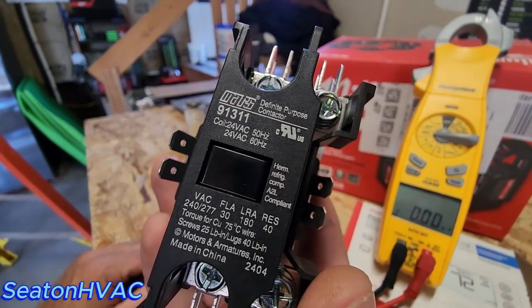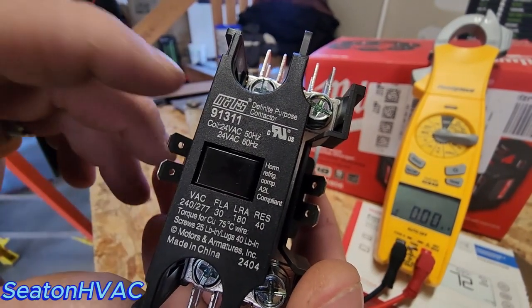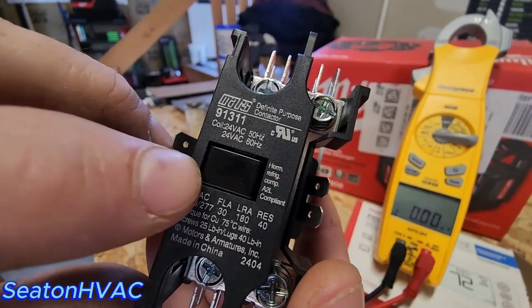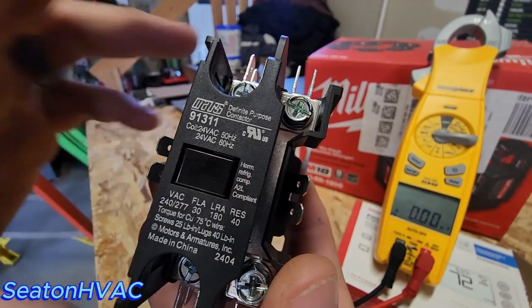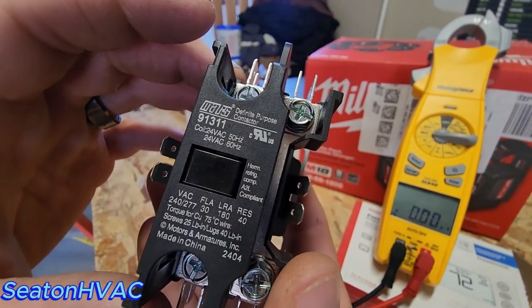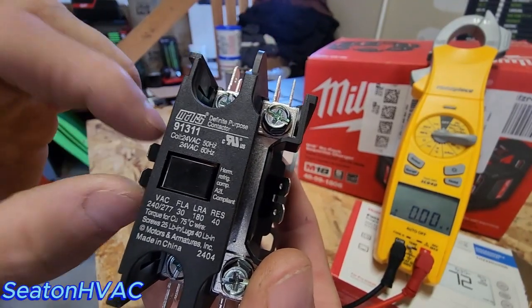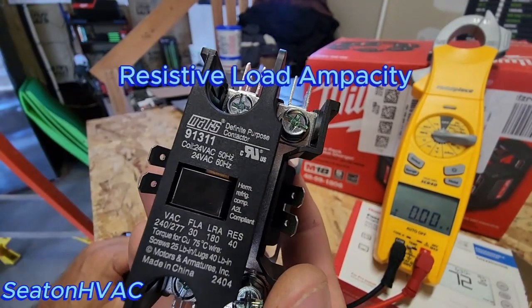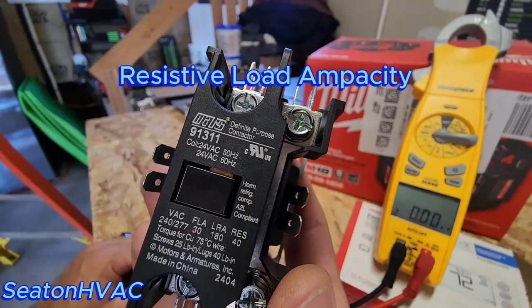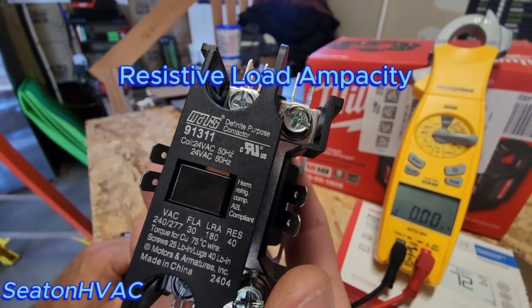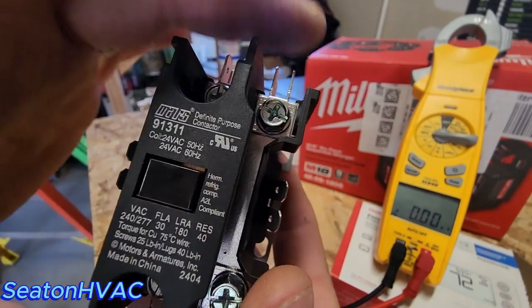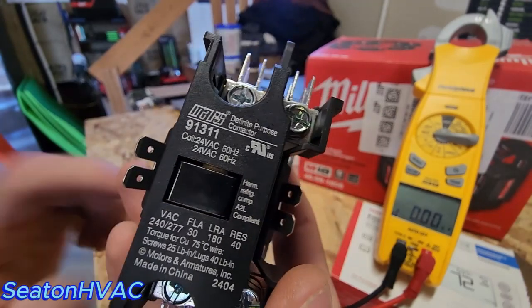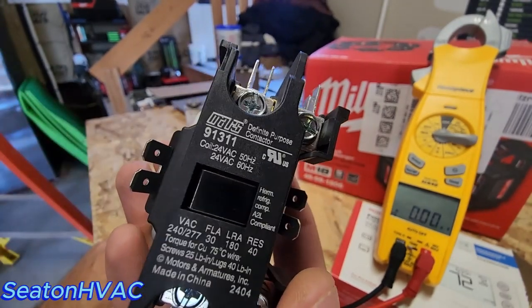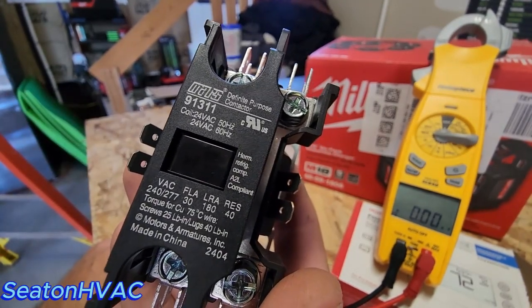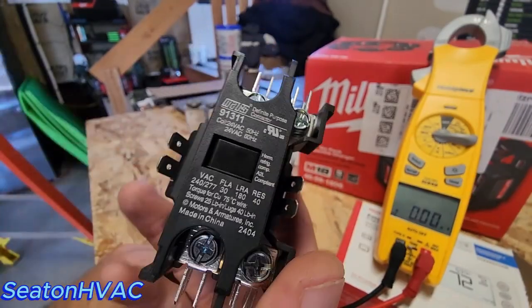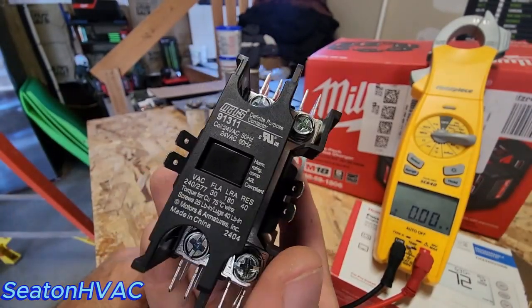It's different than what your full load amps would be. This number is always higher because it has to do with the terminals themselves, not the coil. Your coil only has a voltage and then your hertz readings that are pertinent to it. All these numbers here are pertinent to your 240 volt terminals and your switch. It has nothing to do with the coil. That's why they put these numbers down here. It tells you what to torque your screws to and stuff. Whatever, just tighten it real good with your screwdriver.